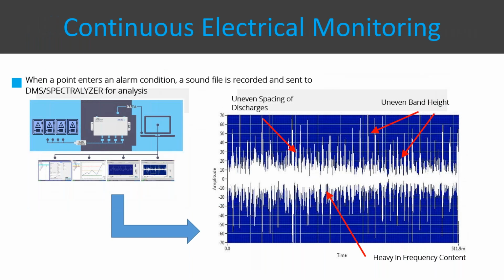So again, a little repeat of what I mentioned earlier: we're looking at uneven spacing of discharges, uneven band height, and frequency content. This lets us, through the alarm notifications we get and through the sound file that immediately gets recorded, tell severity from a remote location.